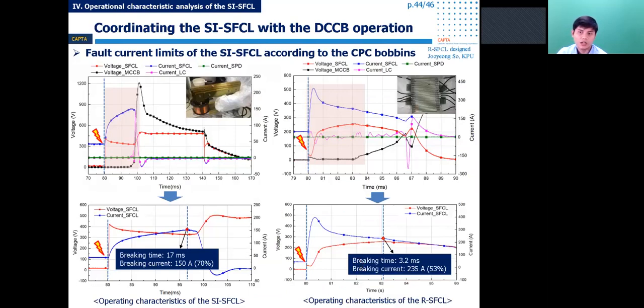The operating characteristics of the SFCL were tested and compared with a resistive SFCL module. In case of using the resistive SFCL, it needs time to increase the resistance during the quench. So there was a very large source current here from the start. Therefore, the circuit breaker can detect the fault and break faster. It's very fast. However, the large source current like that is very dangerous for the power system.